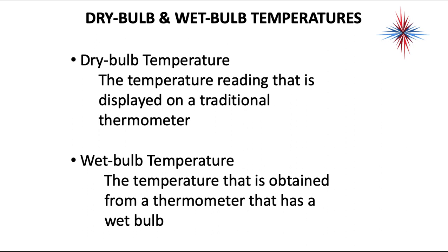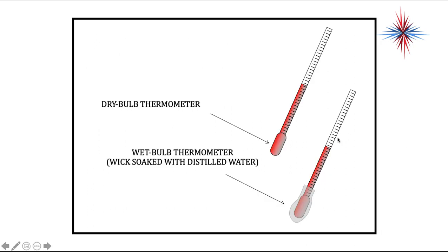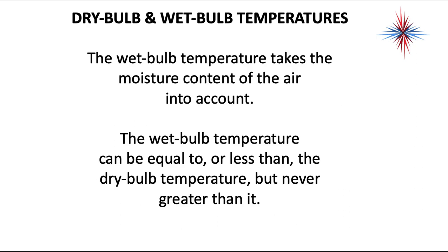We have to understand dry and wet bulb temperatures. A dry bulb temperature is the reading displayed on a traditional thermometer — it does not take moisture into account. The wet bulb temperature is obtained from a thermometer that has a wet wick over the end of it; it does take moisture into account. A dry bulb thermometer could show one reading in the same room as a wet bulb thermometer. The wet bulb temperature can be equal to or less than the dry bulb temperature, but never greater. As water evaporates, it cools whatever it's evaporating from — that's why the wet bulb is always equal to or less than the dry bulb.